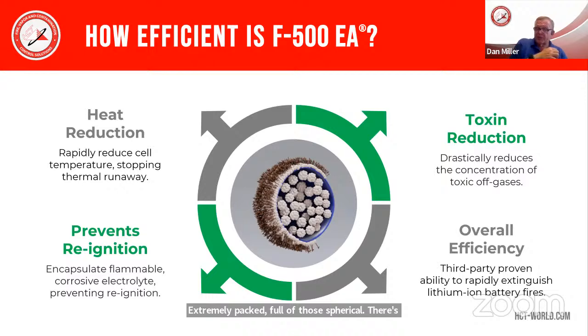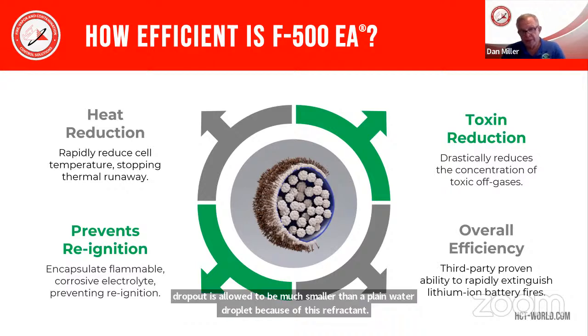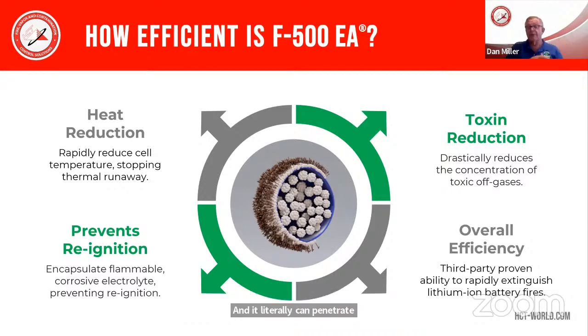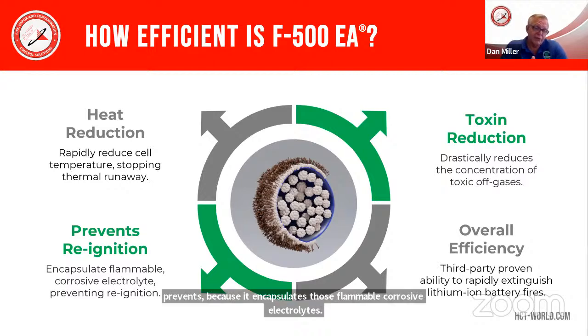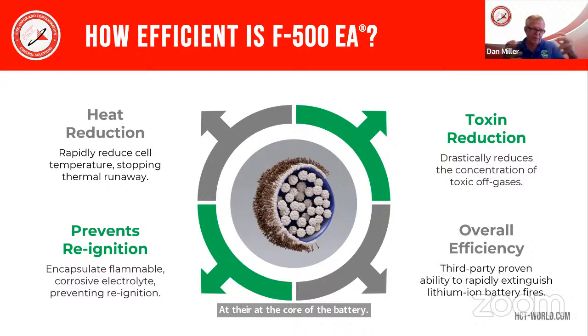The water droplet is allowed to be much smaller than a plain water droplet because of the surfactant, and it literally can penetrate those batteries where they're coming apart at the seams and get in there to the flammable electrolyte and neutralize that electrolyte, as well as cool at least 10 times as well as plain water does at 3% solution. It prevents reignition because it encapsulates those flammable corrosive electrolytes at the core of the battery. It reduces the toxins - we'll talk about how that works in a little bit - but the encapsulation process encapsulates the toxins inside of the spherical micelles.